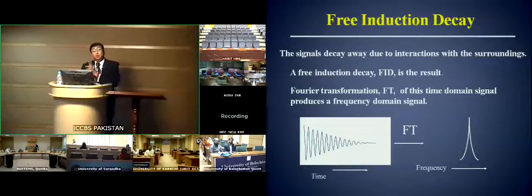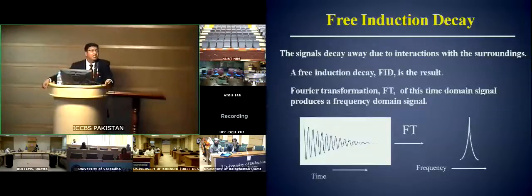Calibrating the pulse is the most important routine which an NMR spectroscopist does apart from shimming, making sure that your magnetic field is homogeneous by using the Z, X, Y, a whole range of different types of magnetic coils. Question?